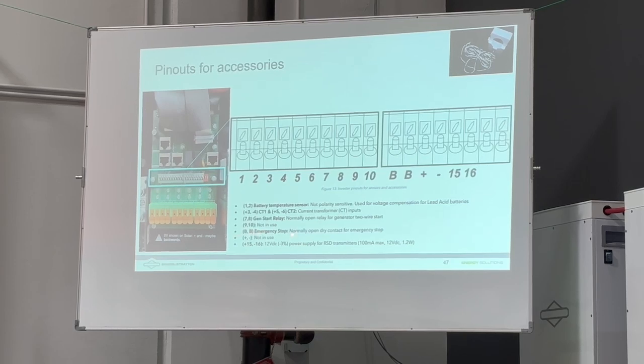Pins, the ones labeled BB here, what I would call 11 and 12, that's where the rapid shutdown button that I have up there is. And that's what is required by fire code, that you have a rapid shutdown. And that should be accessible on the outside of the house, right? Then pins 15 and 16, this is your power supply for your rapid shutdown transmitter.